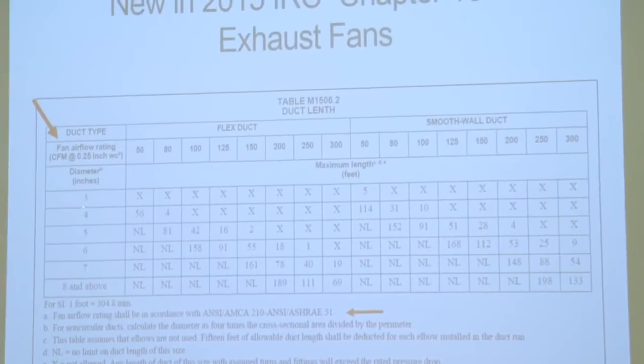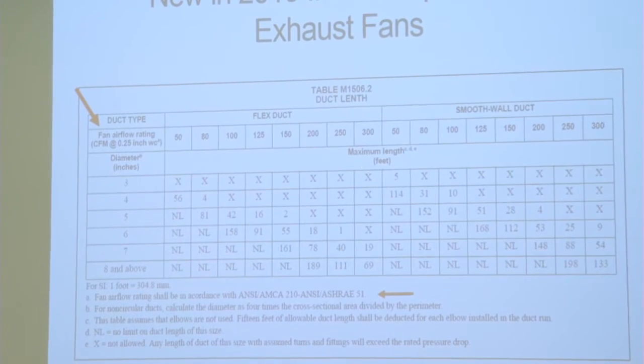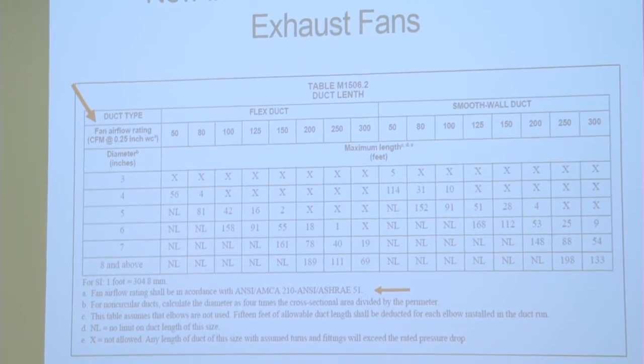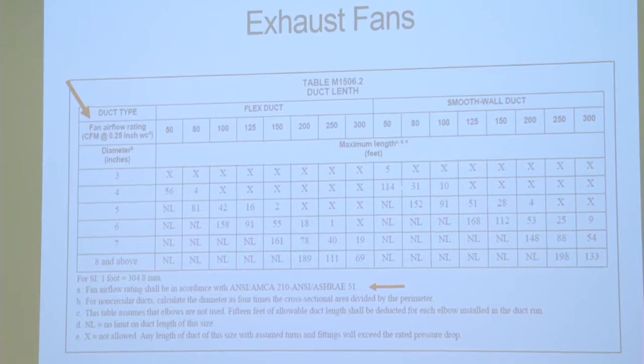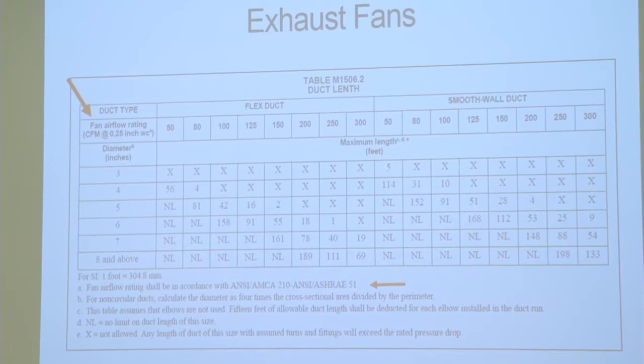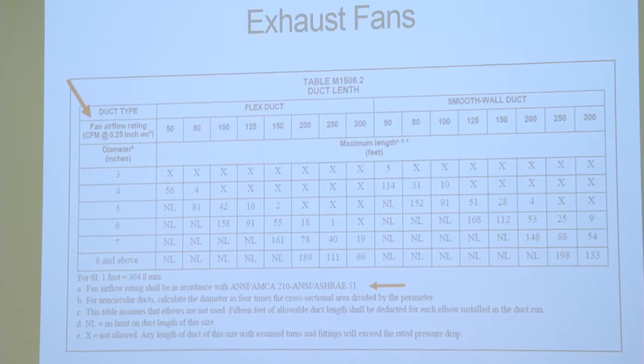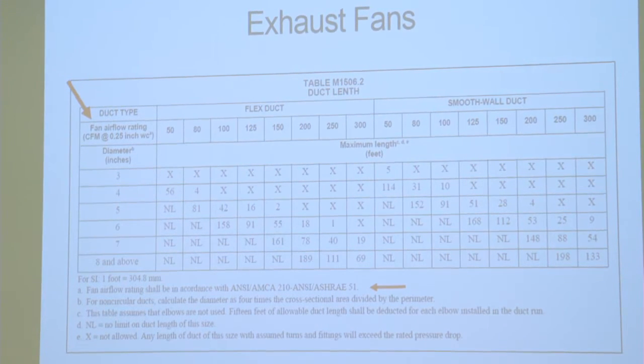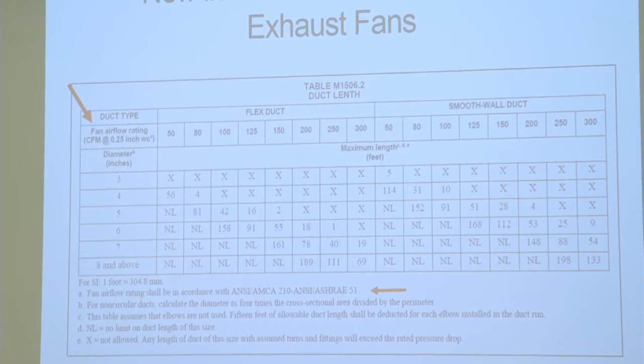So if you were to find a 3-inch fan that moved 50 CFM, we have a table now in the code, and it says if you want to use flex duct and a 3-inch fan, you can't do it ever. If you want to do smooth wall duct, you could put 5 feet of 3-inch pipe on that fan, but you have to take 15 feet for every elbow you put in it. So you can't do that either.